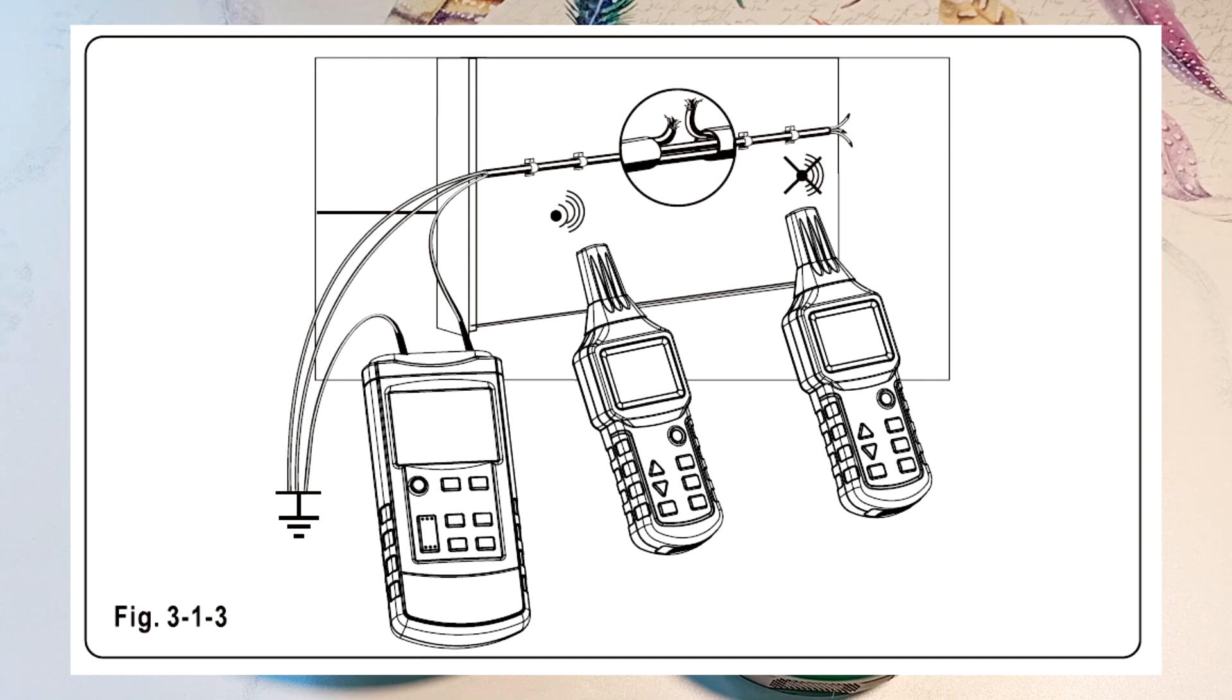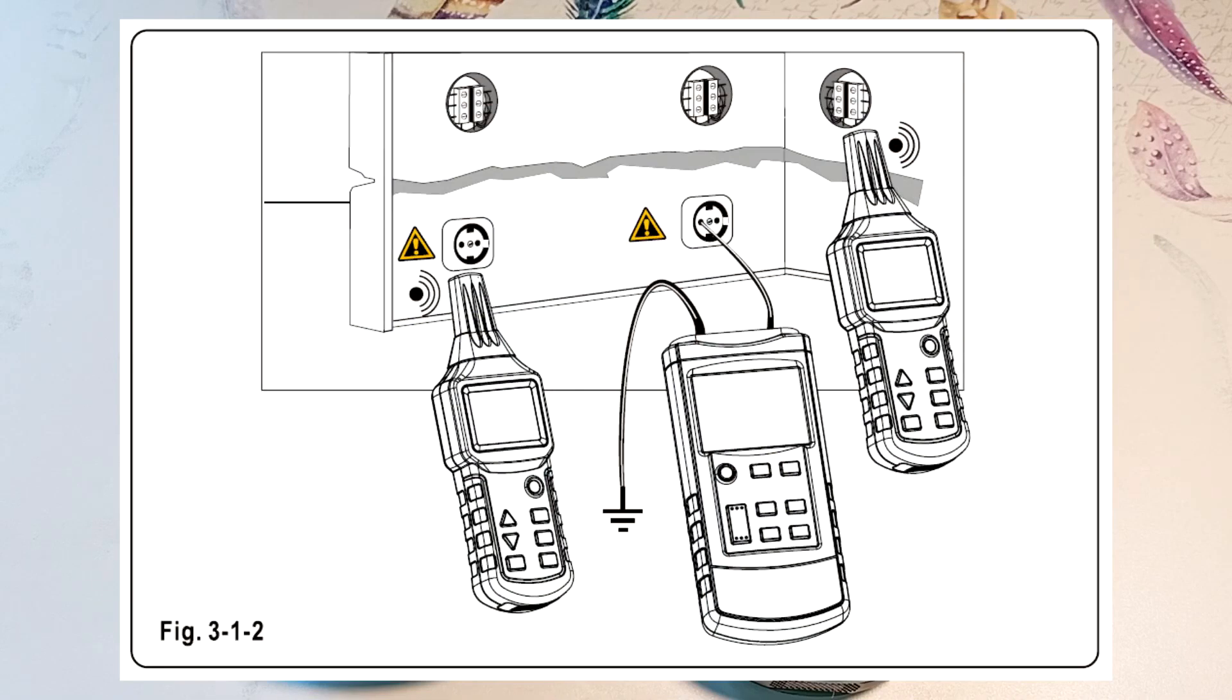When finding breaks, it should be taken into account that the transition resistance at the break must be greater than 100 kilohms. In this figure we find the location of wires, boxes, sockets covered with plaster. We also find line breaks.